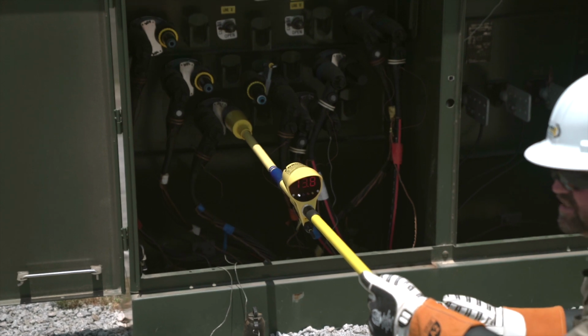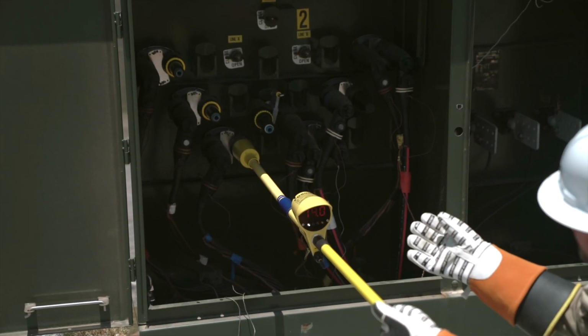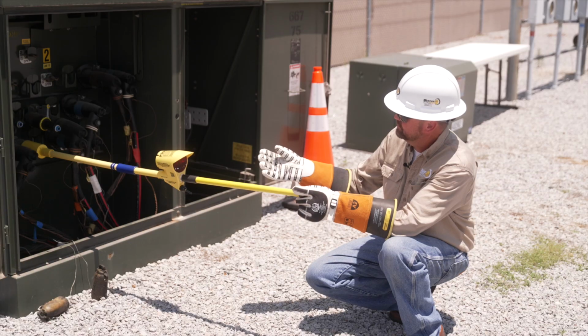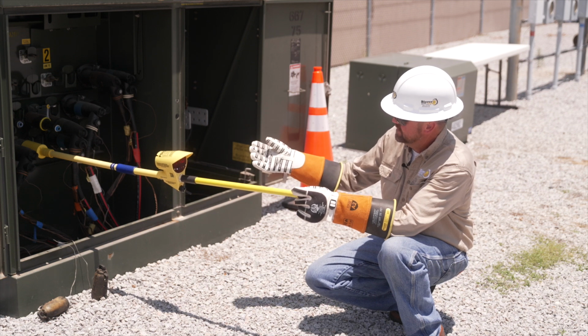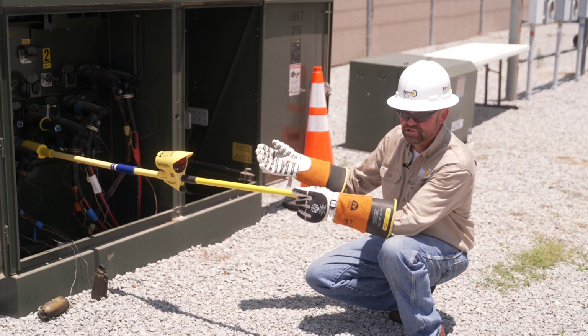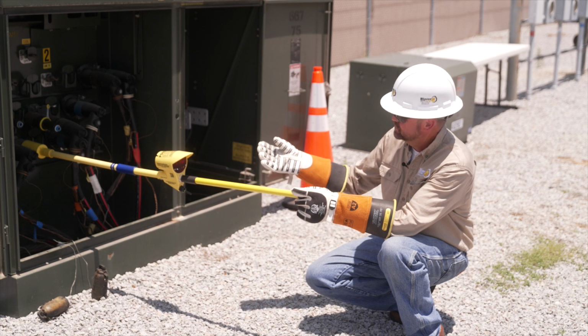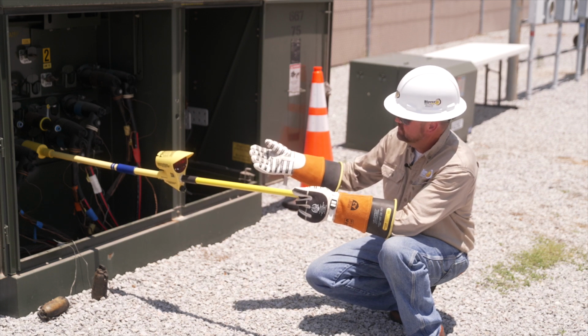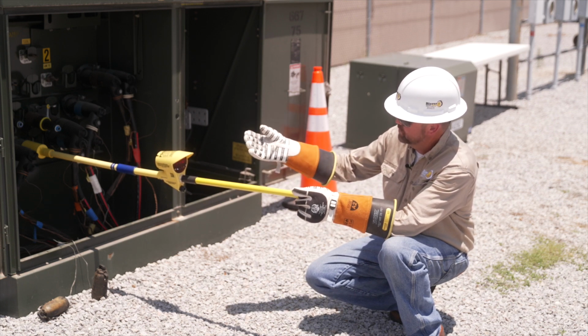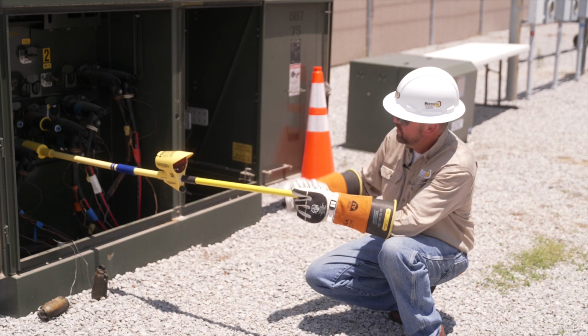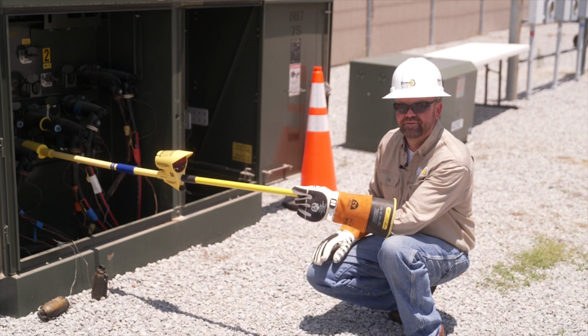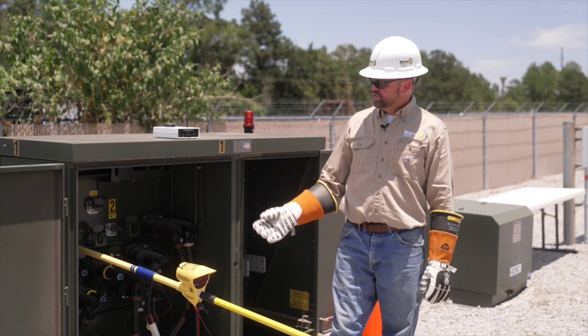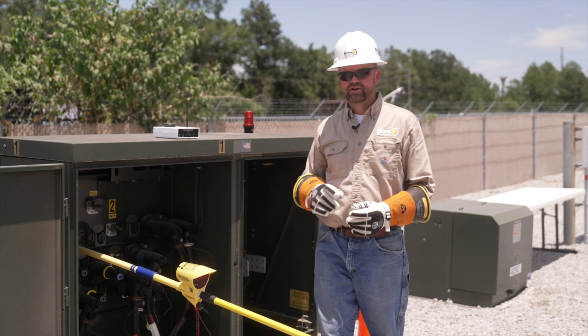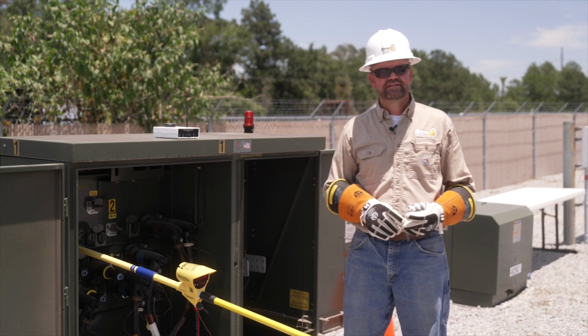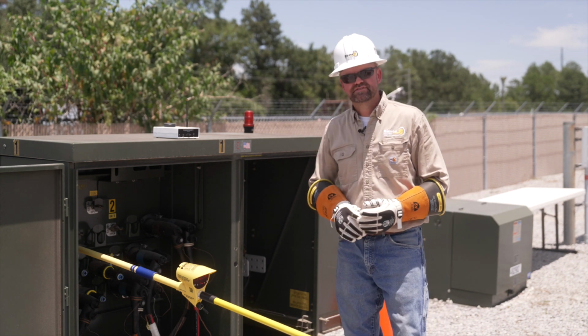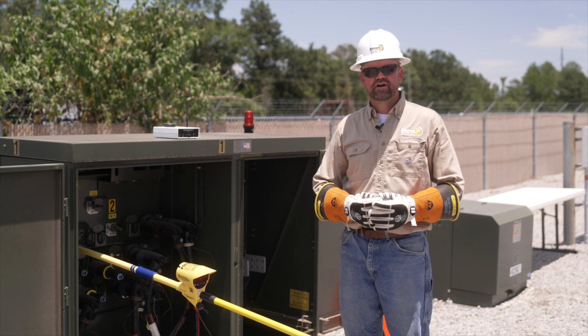So I've done 3 things simultaneous. I've determined my 13.8 kV phase to ground. My H3A bushing is in phase. And I've also determined my sequence. So my H3A bushing is leading my H2A, which is 120 degrees out, and my H1A, which is 240 degrees out. So again, we've done 3 things simultaneous here. We've taken our nominal voltage, we phased, and we phase sequence using our reference probe over here on my overhead conductor.